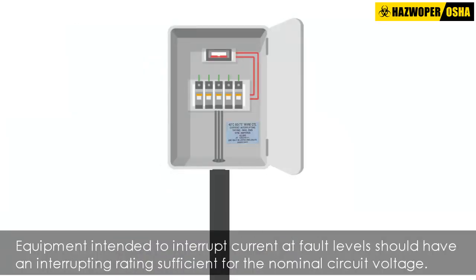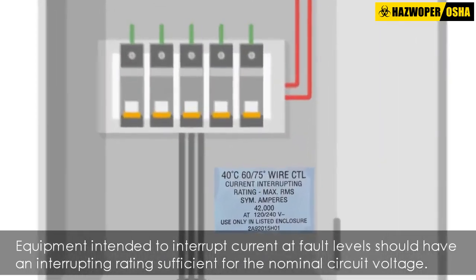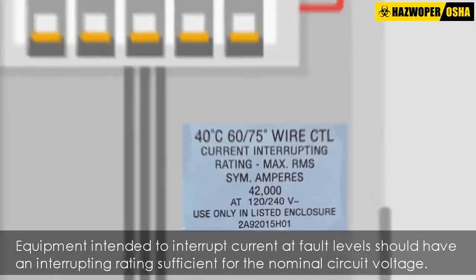Equipment intended to interrupt current at fault levels should have an interrupting rating sufficient for the nominal circuit voltage and the current that is available at the line terminals of the equipment.